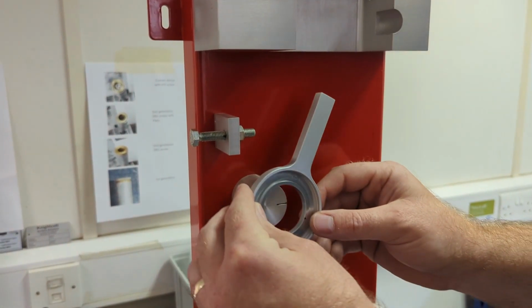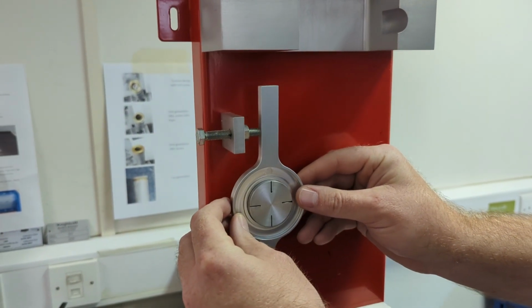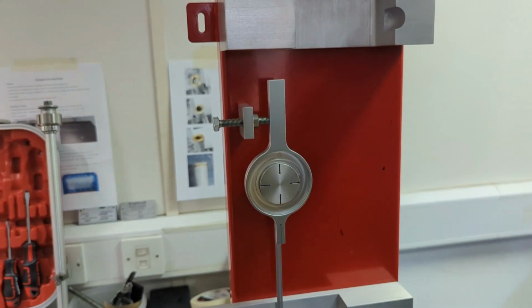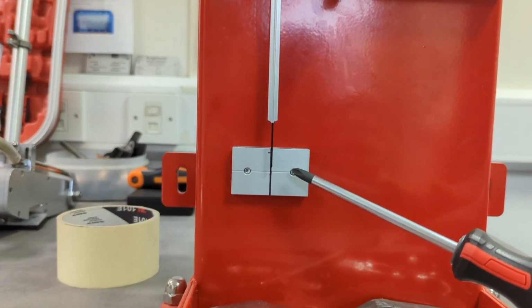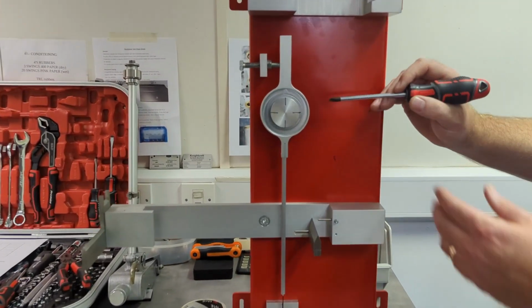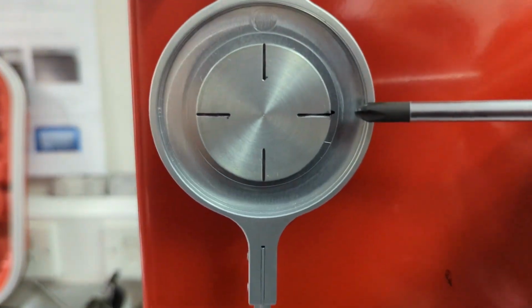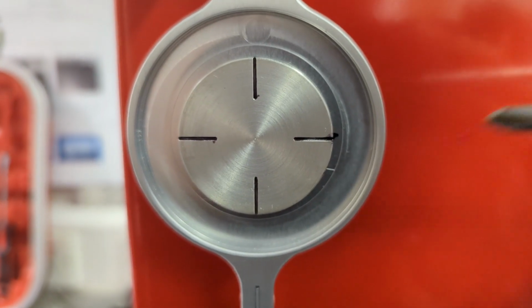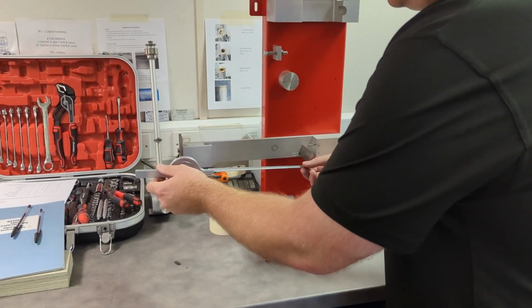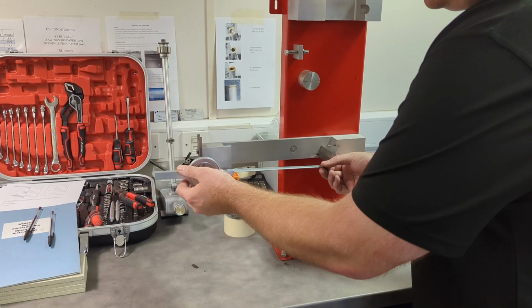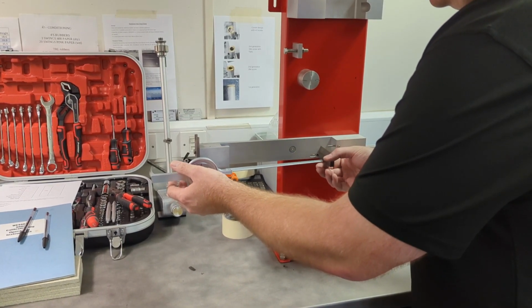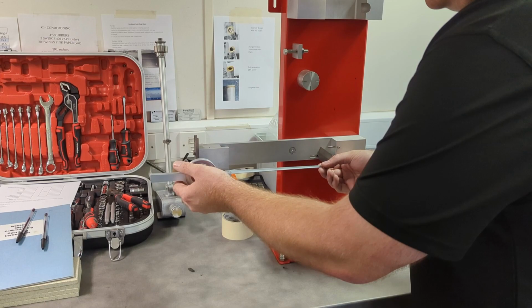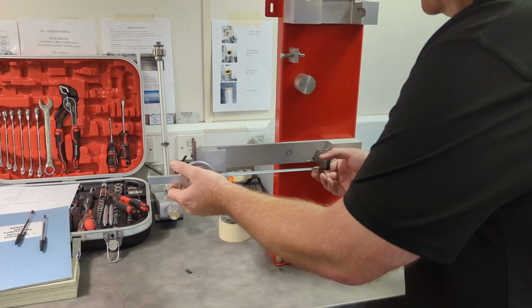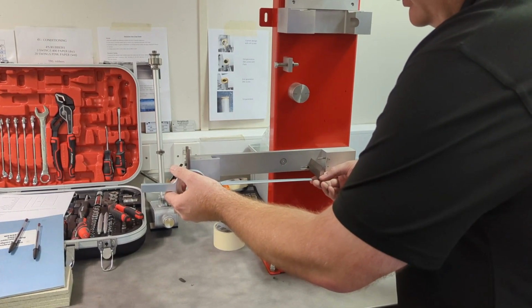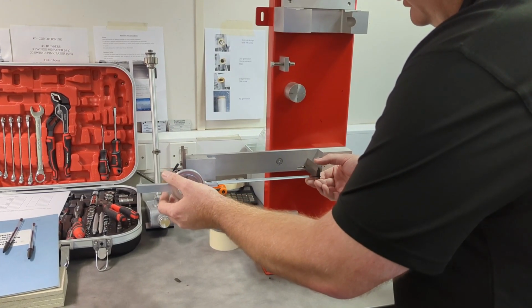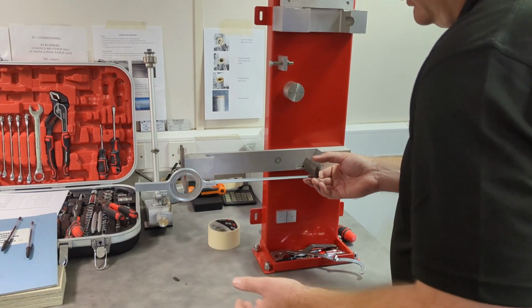The jig provides the ability to check the straightness of a pointer, and marking the inside of the pointer when properly aligned on the jig gives us a mark that we can then use to check the pointer balance. When placing the pointer with this mark aligned on the left-hand knife edge, a perfectly balanced pointer will align with the mark on the right-hand knife edge, as shown here.